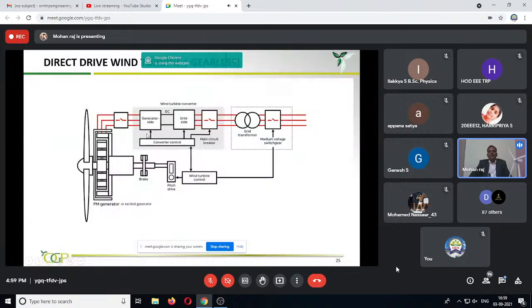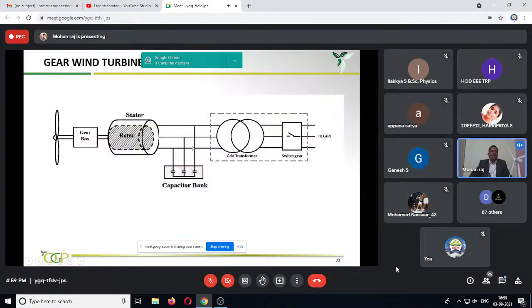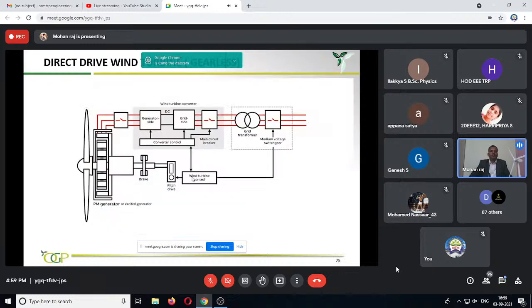So this is a single line diagram of the direct drive turbine. You see, in a geared wind turbine, it is directly synchronized to the grid, because if we are using an induction generator, when it goes above the synchronous speed, it will automatically sync to the grid voltage and grid frequency. But in a gearless wind turbine, a lot of conversions are required, and also it will be light in weight. If it is light in weight, we can capture more power from the wind. So if it is a geared wind turbine, you are capturing about 40 percent of the energy from the wind, but in the direct drive turbine, it goes up to 45 to 50.